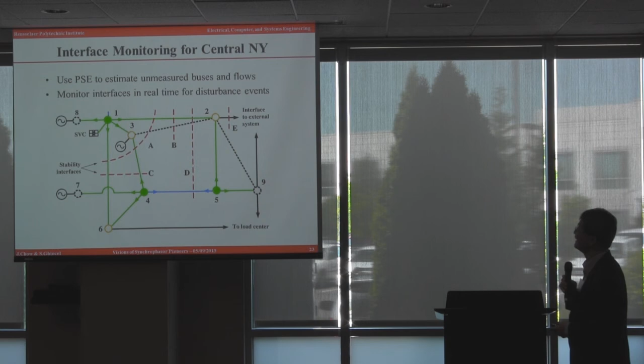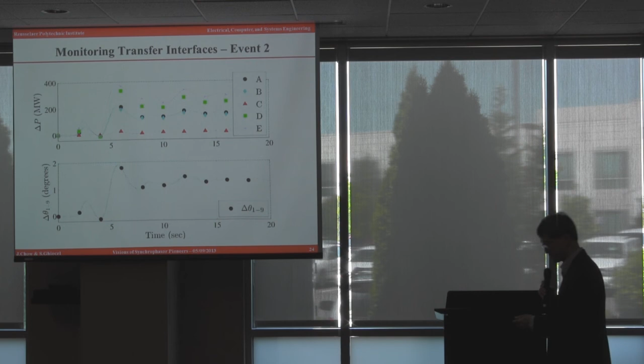In the first column, the mean TVE is slightly over 1%, but there's no angle correction. If we also correct the angle bias, now they're all within 1%. And of course, the standard says you have to be less than 1%. So the system actually works well. You can also monitor the interface calculation. For example, with directional flows and a disturbance to the east, all your east-west lines will see a difference in the flow, and the north-south line doesn't see a flow. All these things just tell us the power system works just as expected.